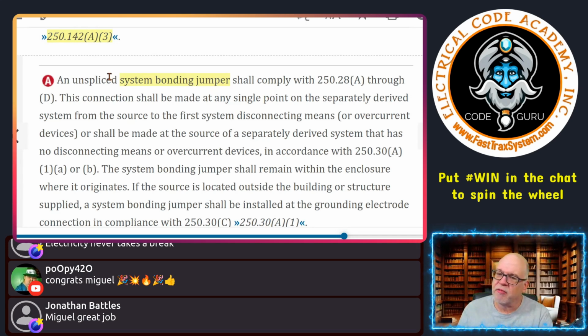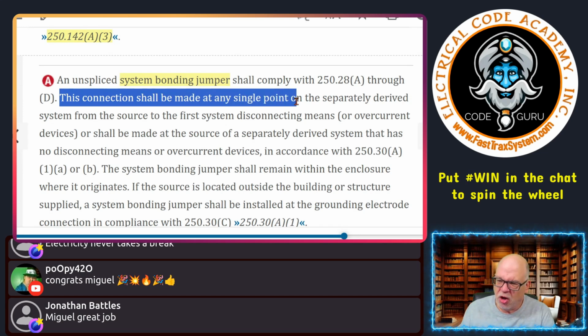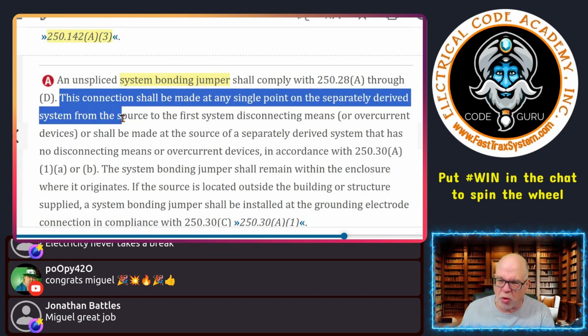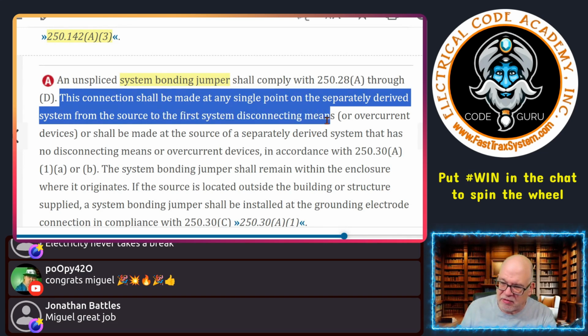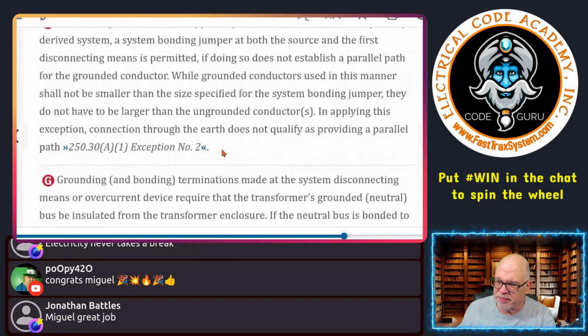All right, so an unspliced system bonding jumper shall comply with 250.28(A) through (D). So this is going to talk about the type of connection, copper, aluminum, what it needs to be, all those type of things, and sizing, by the way, which is ultimately going to send you to 250.102(C)(1) for sizing. It says, this connection shall be made at any single point on the separately derived system from the source that is in the transformer to the first disconnecting means. Which in this case, I'll just highlight that, is right here.